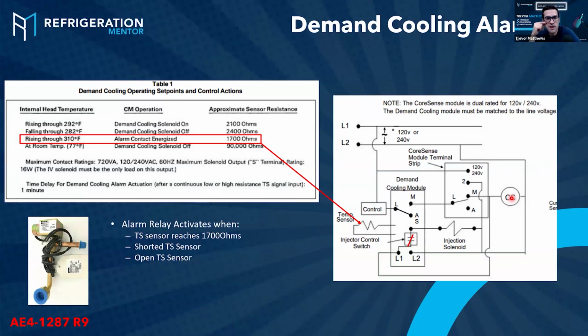On discharge / condenser temp, how would you estimate if you need injection on a system that is not operational yet? Is it similar to what my highest design temp is? Oh, that's a great question. So what you need to do is go into the compressor software, and I can show you how to do that. As long as you know your design conditions, you can figure out if it's going to be injecting or not. Now, if your condenser gets plugged, or your water tower is not working properly, you don't have the proper flow, whatever it is, that won't be taken into account. But yes, you can find that out before. And that was kind of from the operation envelopes. And I'll show you that, Tom, in a minute here.